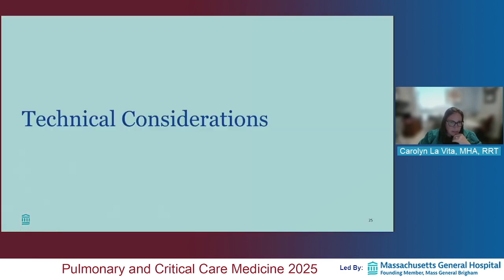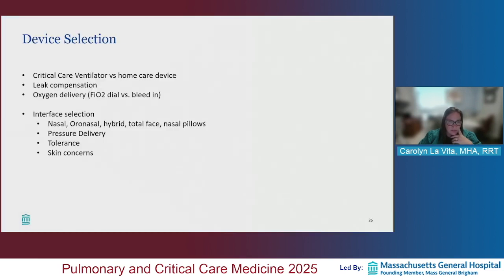As I mentioned, there are many technical considerations with non-invasive respiratory support, really non-invasive support for many different disease processes. The primary one is device selection. You can either use a critical care ventilator or a home care device. Some of the differences are things like leak compensation. A critical care ventilator has the ability to measure the leak and to actually either increase the flow or the pressure to maintain the level that you have set. So often when the patient's in acute respiratory failure, you'll get a higher success rate using a critical care ventilator because it can overcome those leaks in the system.